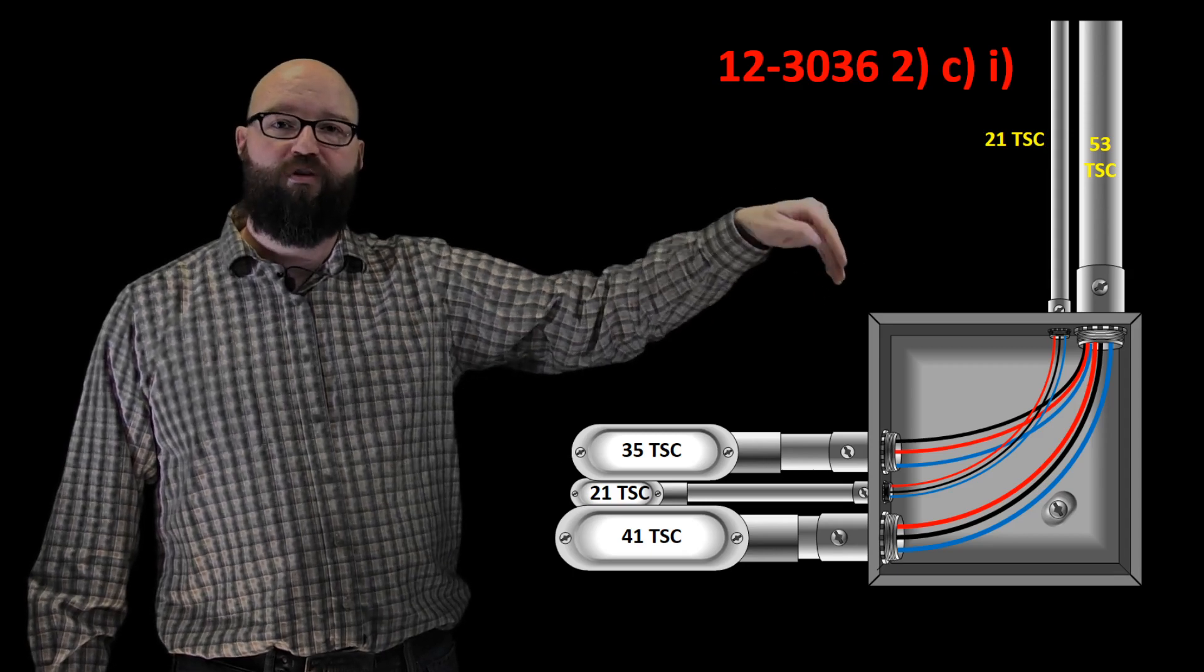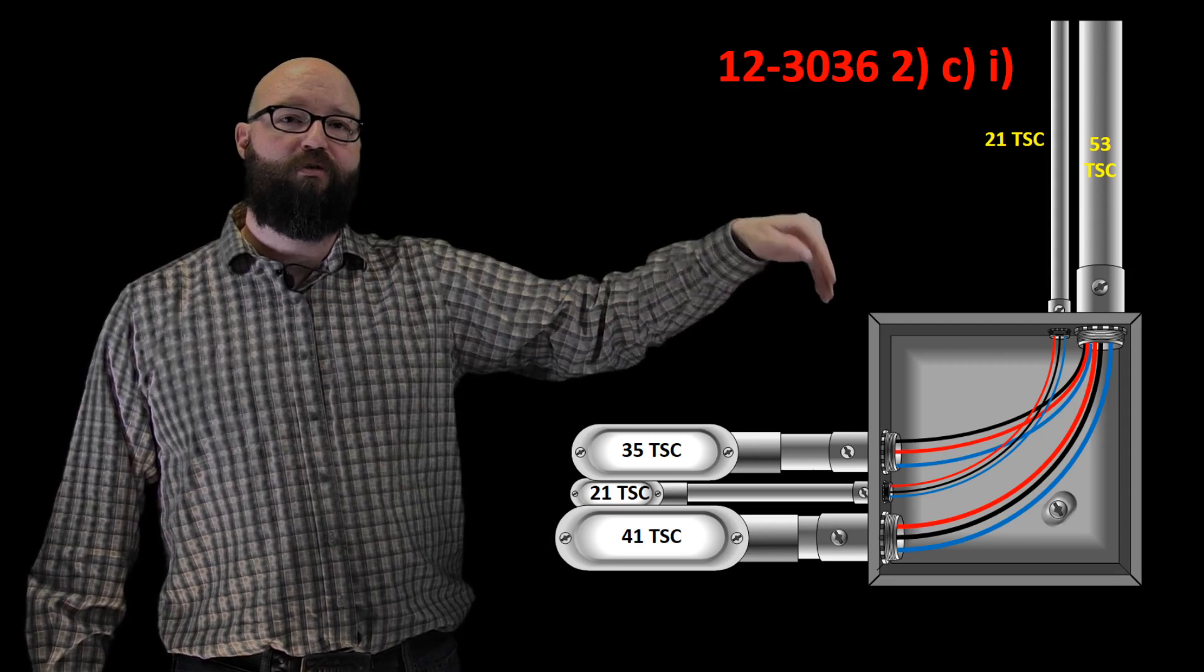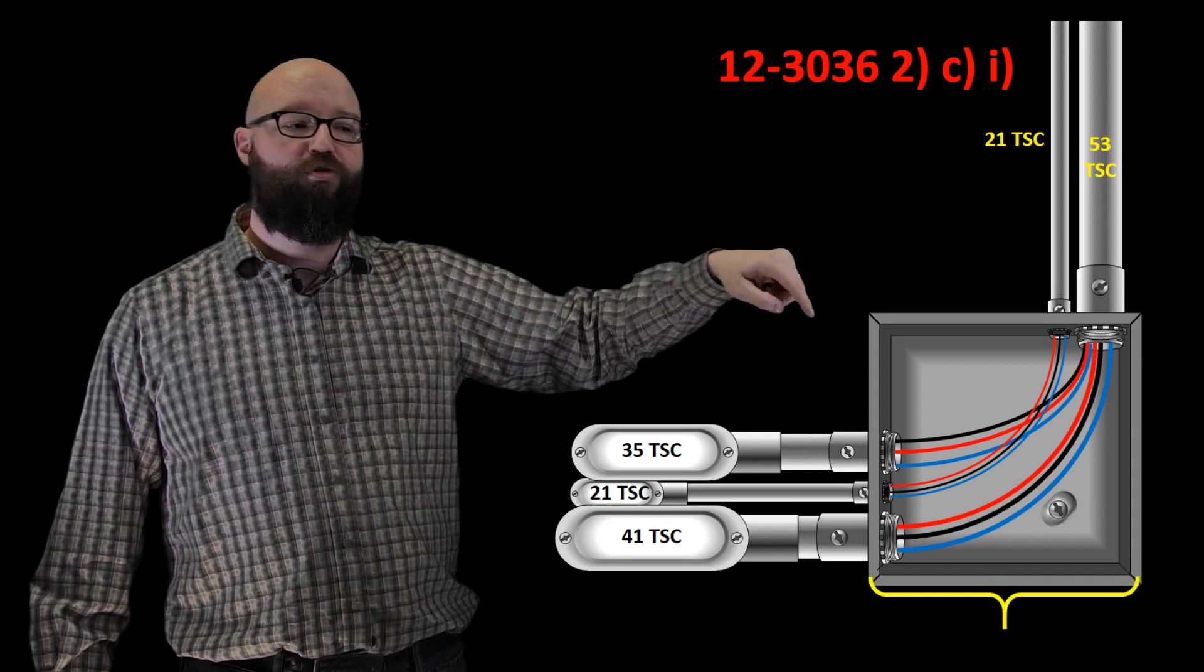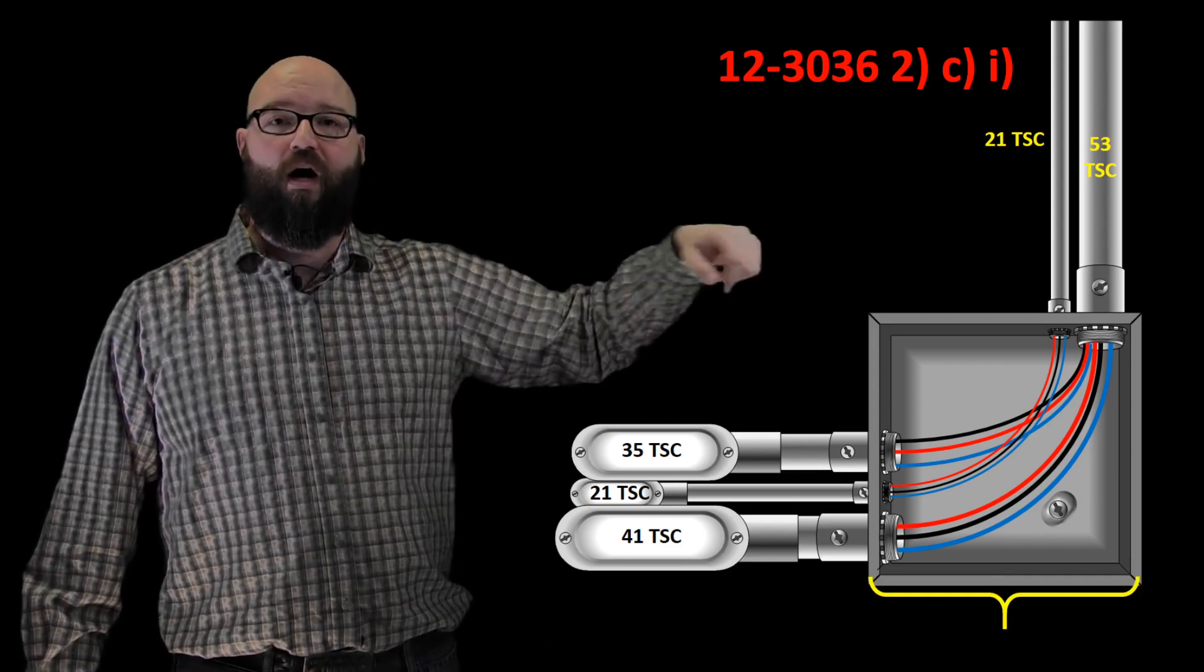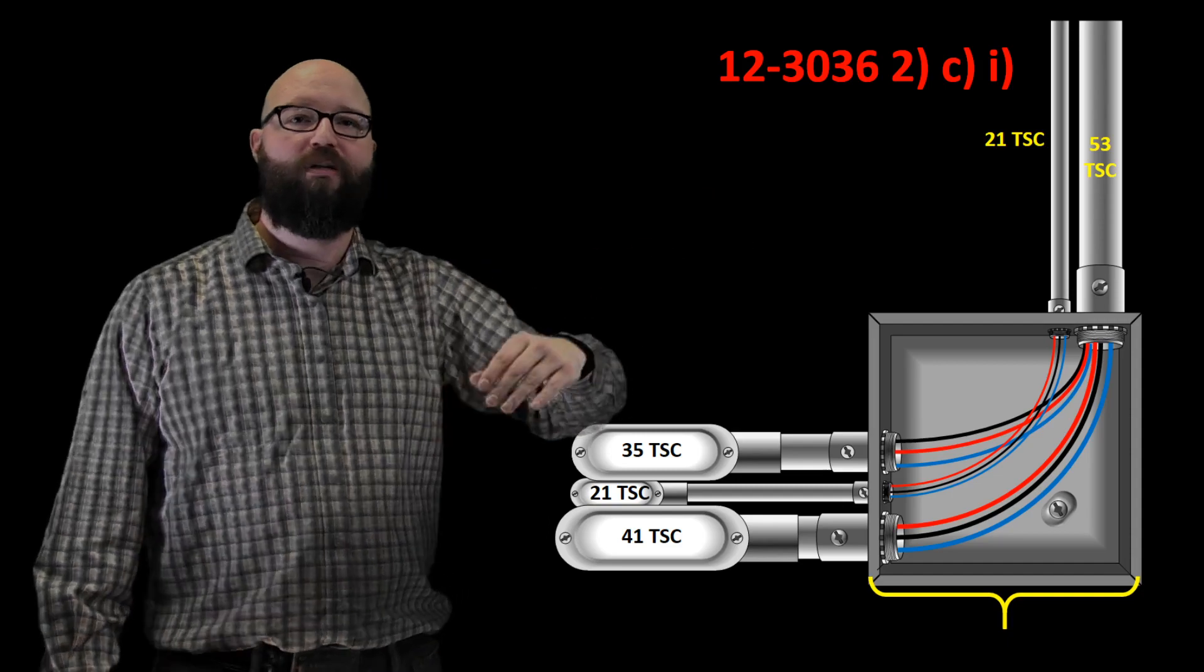The raceways that enter this wall, we want to make sure that we observe the proper bend radius for the conductors that exit those conduits. In order to do that we need to figure out what is the minimum dimension to the opposite wall for where those raceways enter. So to do that if we read in 12-3036, what it tells me we're gonna do is take six times the largest trade size diameter.